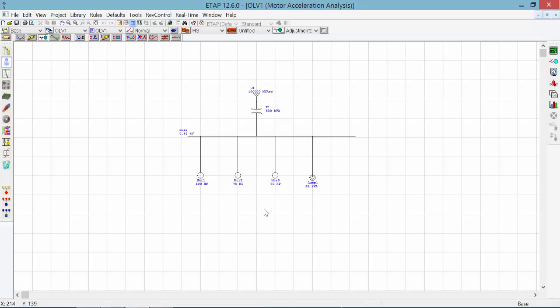But using dynamic motor starting, we will see, considering the characteristic of the load being connected to the bus and using means like variable frequency drive, VFD, we can minimize the impact of the loads at their inrush moments by leading them smoothly to their full load amps. Now let's start the static motor starting analysis by clicking on its icon on the right side toolbar.